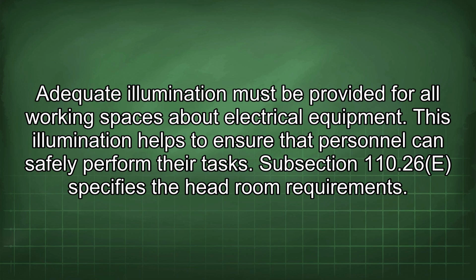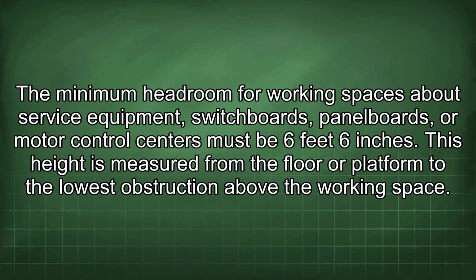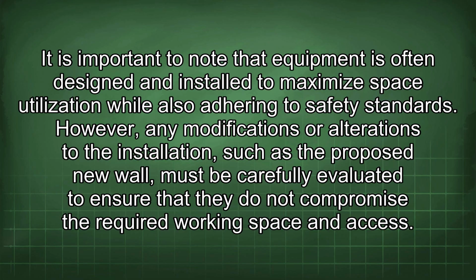Subsection 110.26e specifies the headroom requirements. The minimum headroom for working spaces about service equipment, switchboards, panelboards, or motor control centers must be 6 feet 6 inches. This height is measured from the floor or platform to the lowest obstruction above the working space. It is important to note that equipment is often designed and installed to maximize space utilization while also adhering to safety standards. However, any modifications or alterations to the installation, such as the proposed new wall, must be carefully evaluated to ensure that they do not compromise the required working space and access.